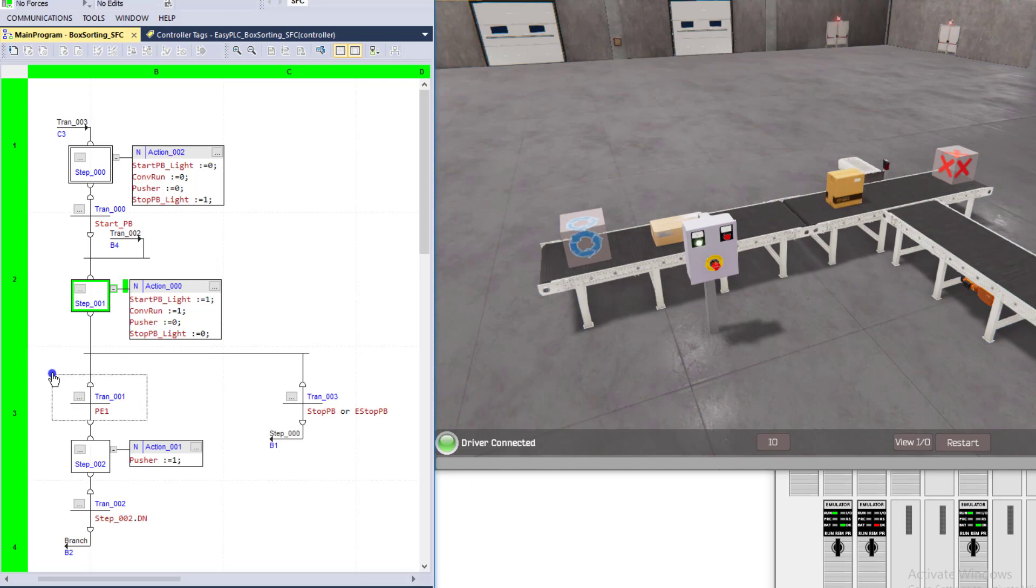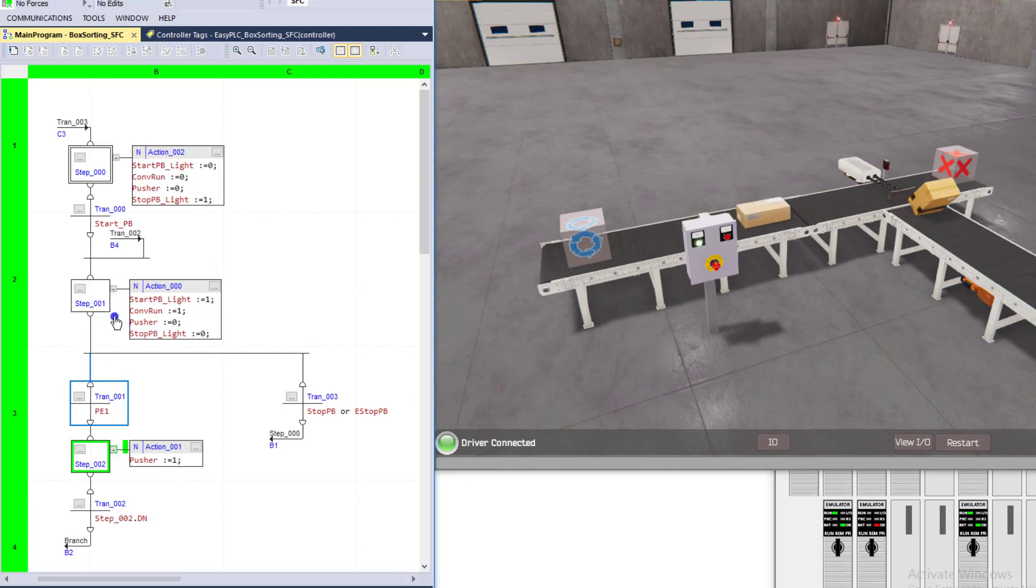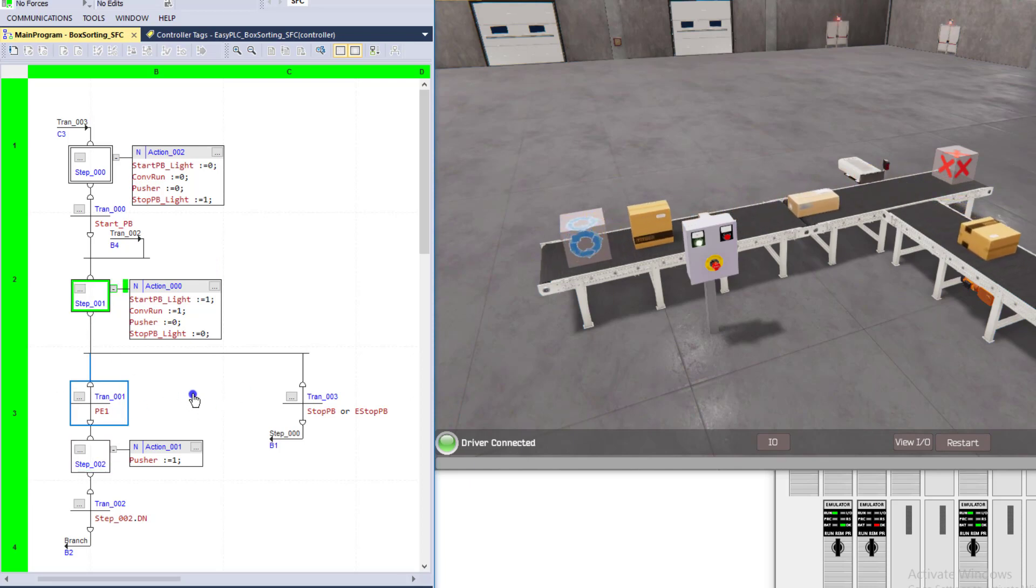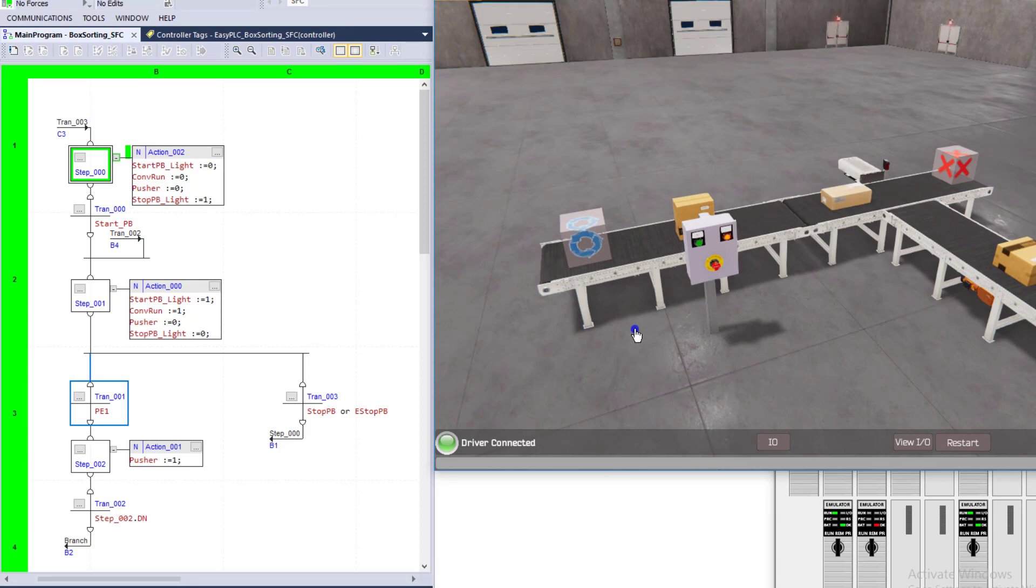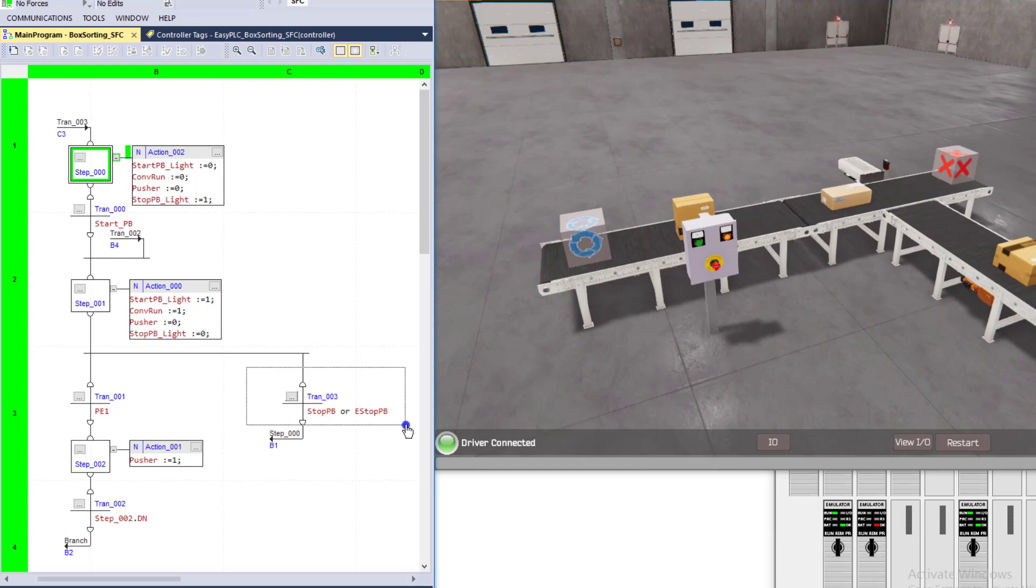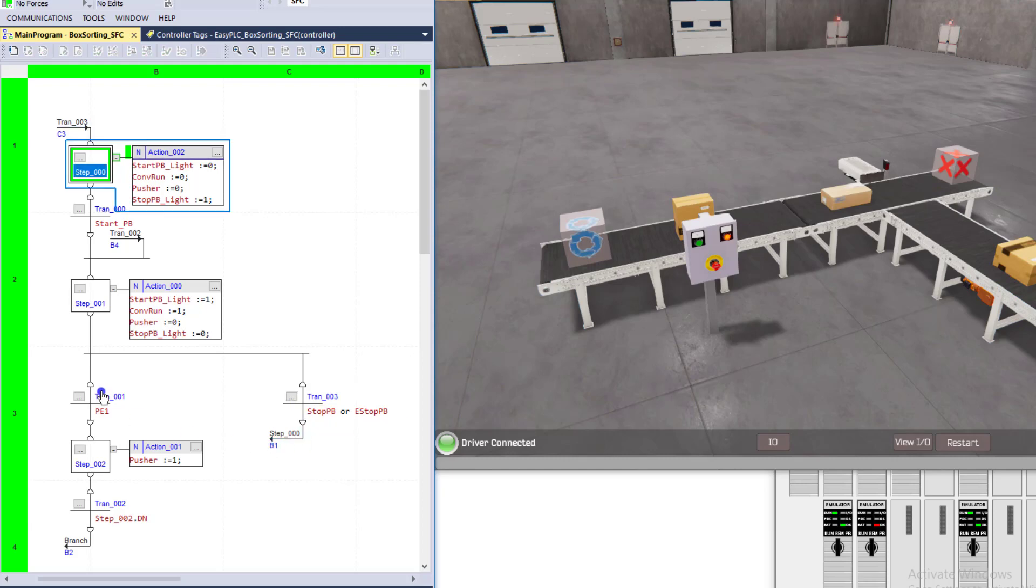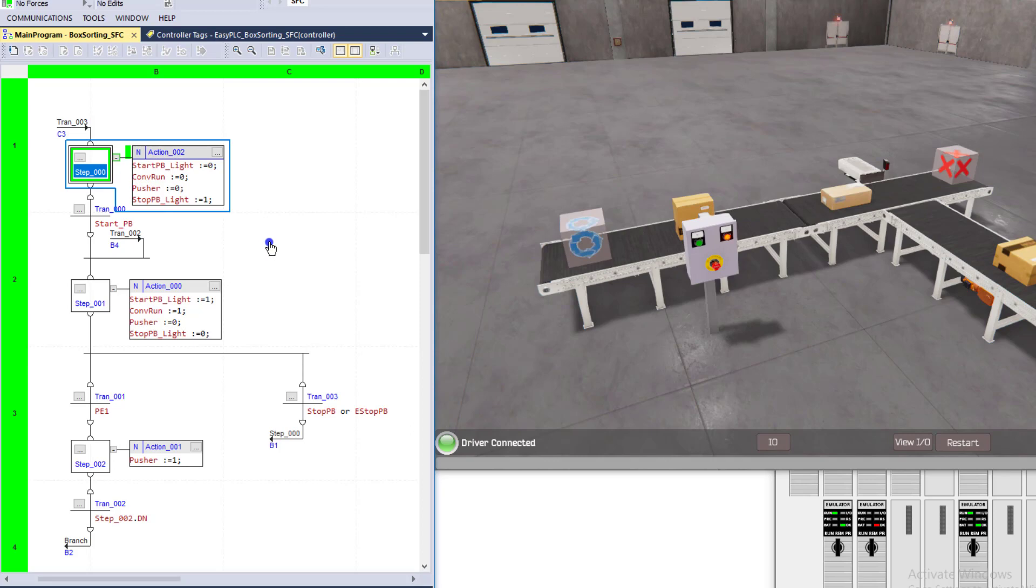So when you're at a certain point, each one of these, like right now, we're waiting on either the box to be a certain height or a push button to actually be active. So if I hit the stop push button right now, you can see that it's going to be stopped, and that's just because in that transition, that tag, that stop push button was a one, so it allowed it to travel through and go back to step 00, which again shut the whole system off because we're not running it.